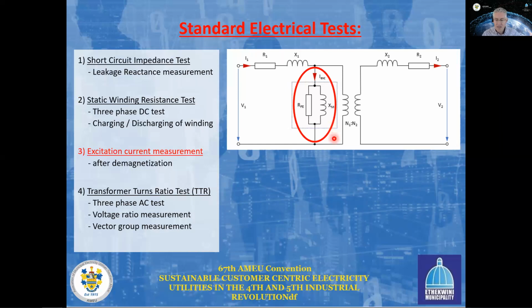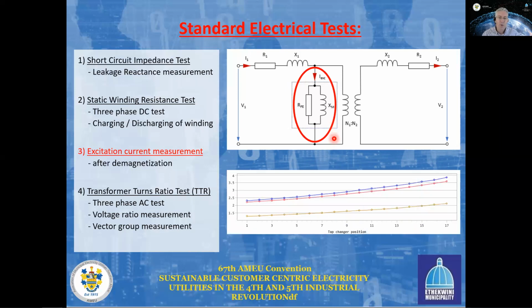And then the results that you get will look something like this, where the currents measured for the outer phases of a star winding are higher than the currents measured for the center phase. The reason being the way that the flux distributes inside a 3-limb transformer, we'll typically find that the center phase can be anything up to 40% less than the outer phases. The outer phases, because the transformer is symmetrical, should be the same. They should be virtually on top of each other.